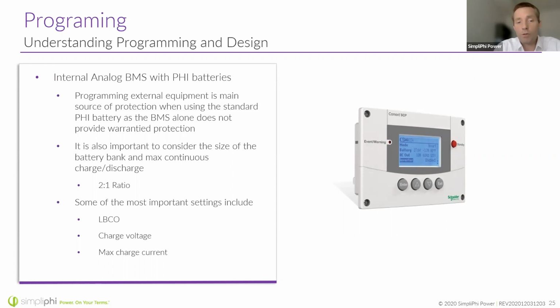It's also important to make sure the charging current is set properly, so that you're charging and discharging your batteries at a rate of C/2. So again, just because a battery has a battery management system does not mean you don't have to set the rest of the equipment up properly.